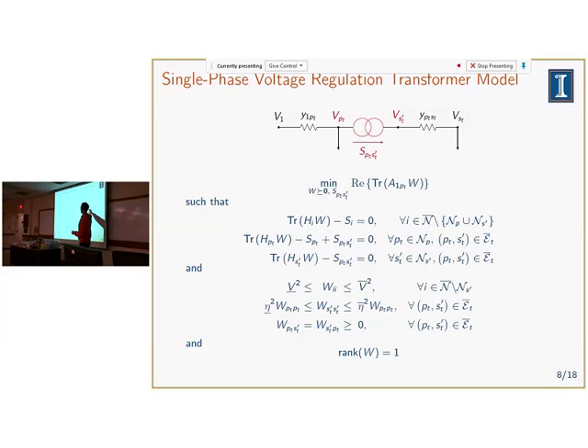Our minimization problem looks like the following: we're minimizing losses here. This is just the power coming from the feeder that minimizes system losses. This is the traditional power flow on every bus except the primary and secondary sides. This is the power flow on the primary side, where the power that goes around the transformer acts as a load. Then this is the power flow on the secondary side, where that quantity acts as an injection, and we limit the diagonal entries to plus or minus 5%, around 1 per unit.